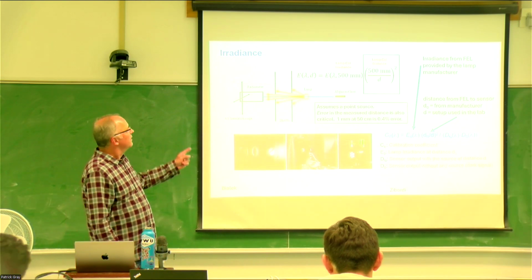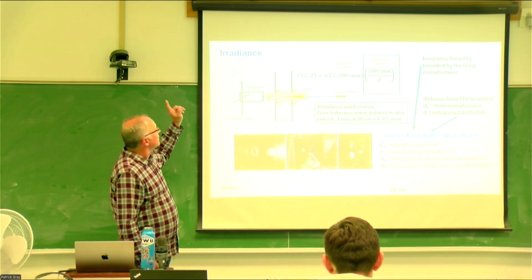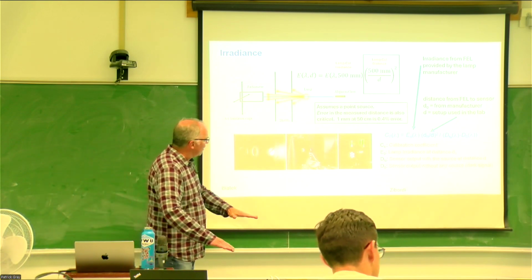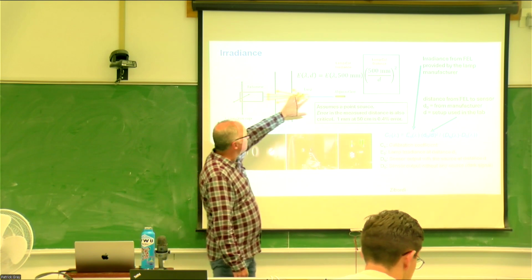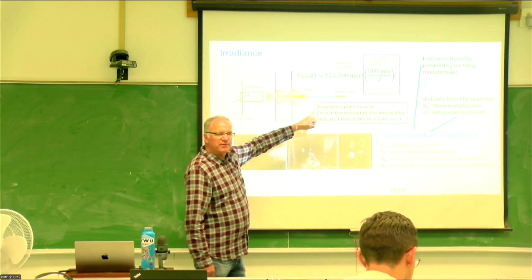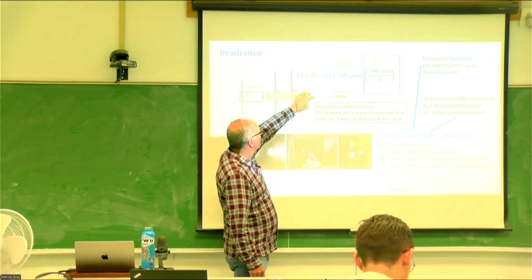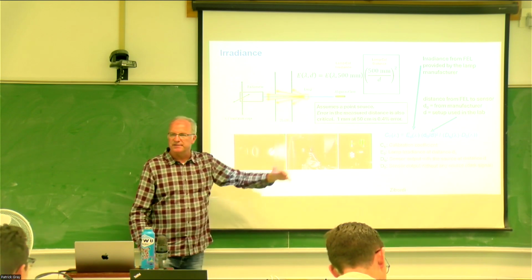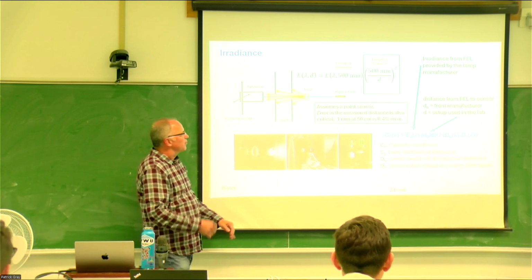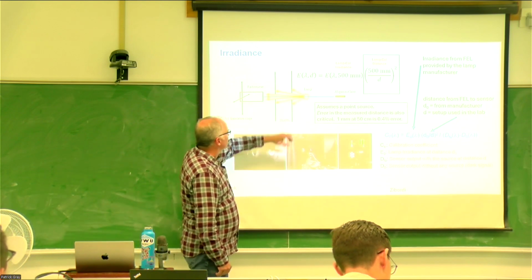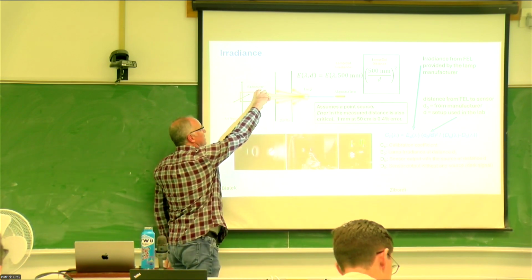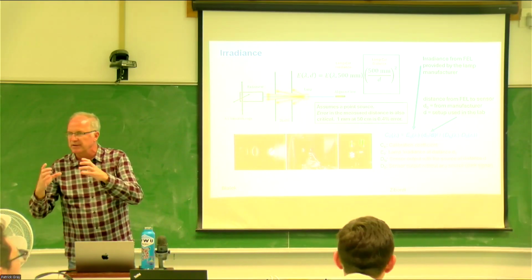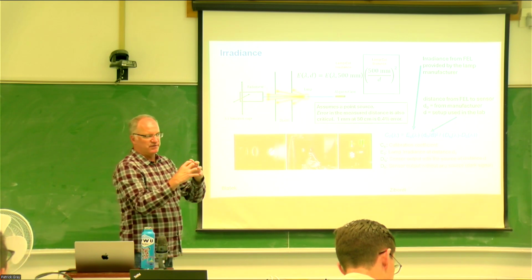Okay, so we're going to go over the calibration process for irradiance. Looking down on this setup, you have an alignment laser and, set at some distance, your FEL lamp. Now what you have are these shields, we call them baffles. They're adjustable baffles. What you're trying to do is create a little cone of light that doesn't massively overfill your sensor, but fills enough of your sensor.